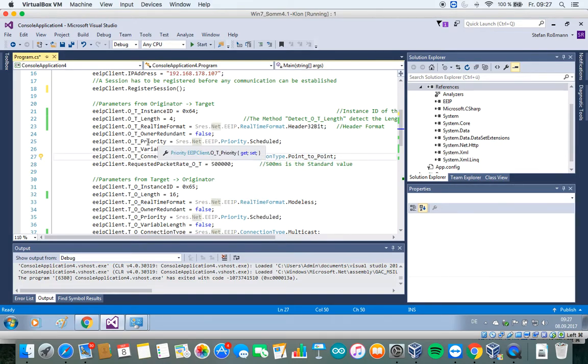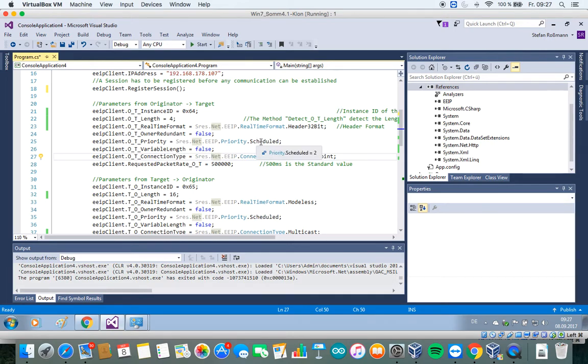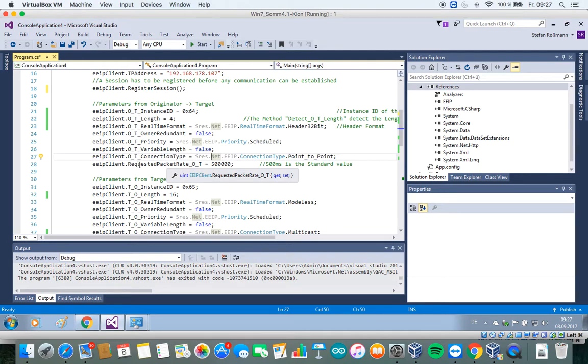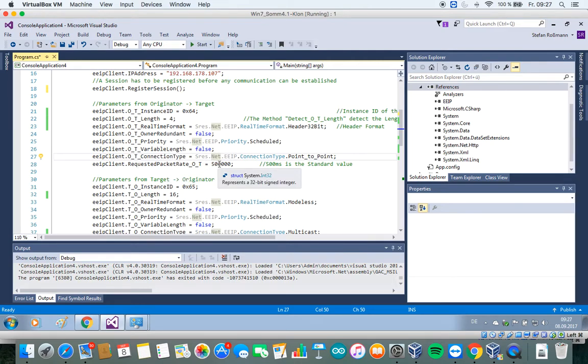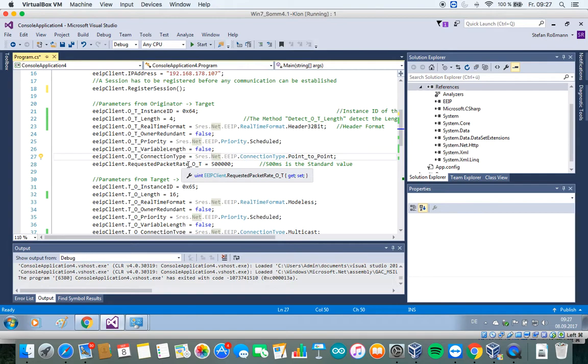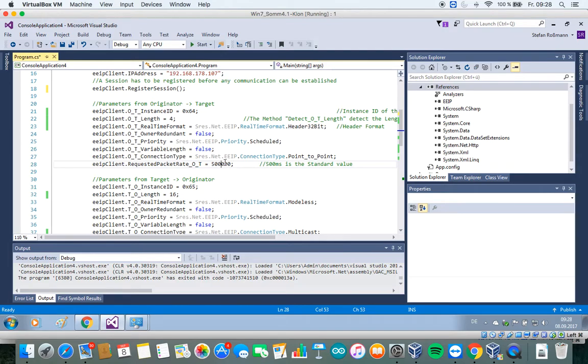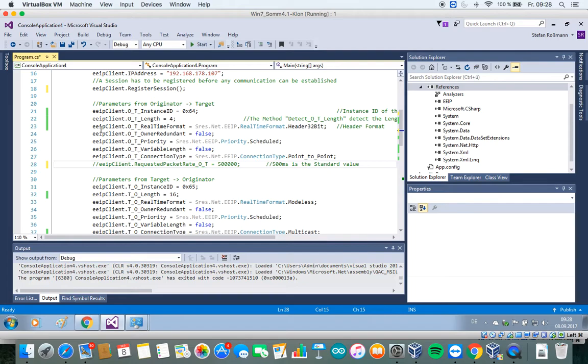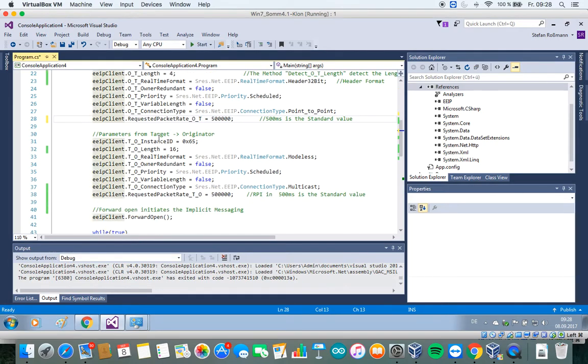The scheduled priority means that our device expects an implicit messaging packet every 500 milliseconds. So this is the standard value. The requested packet rate expects a value in microseconds. So these are 500 milliseconds. So I could also get rid of this, it's just for demonstration.